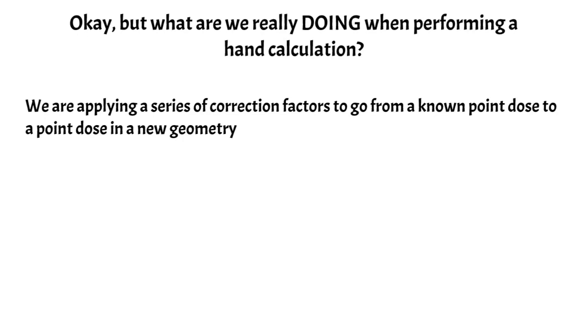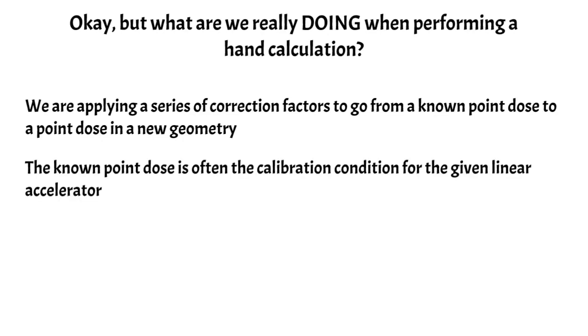So all of that generally makes sense, but it's a little unclear what we're actually doing when we're performing one of these hand calculations. What we're really doing is we're taking a known point dose and we're applying some series of correction factors to that known point dose to get a new point dose in some new treatment geometry. The known point dose that we are altering is often established during the commissioning process and is also called the calibration condition for the given linear accelerator.